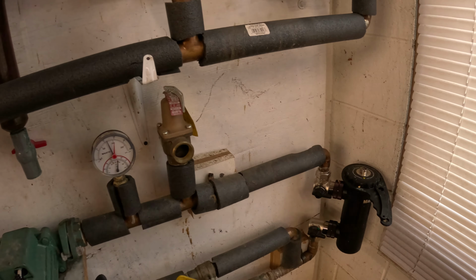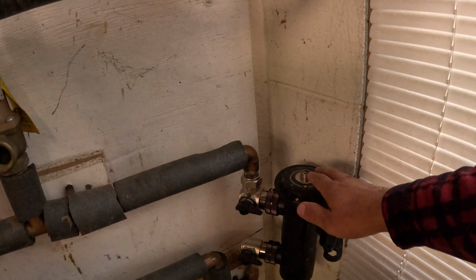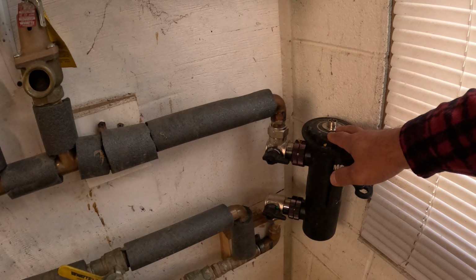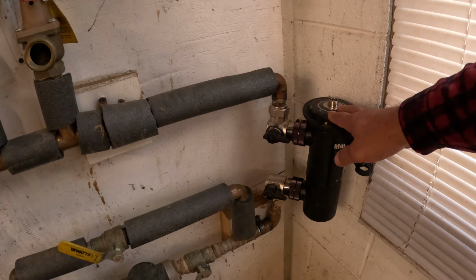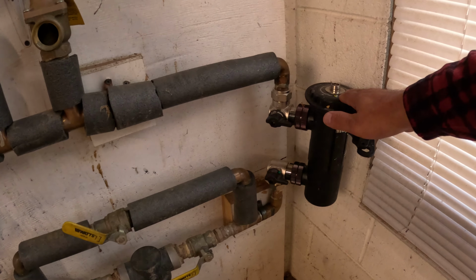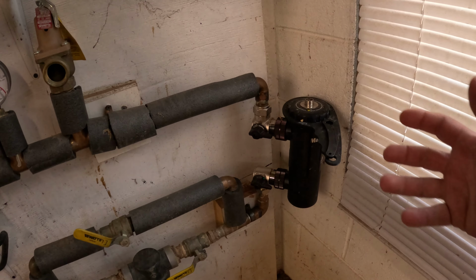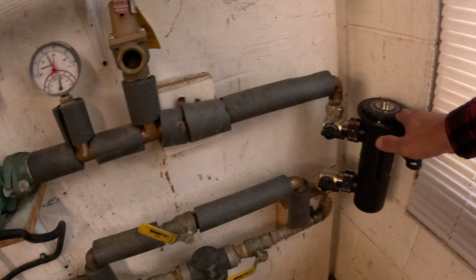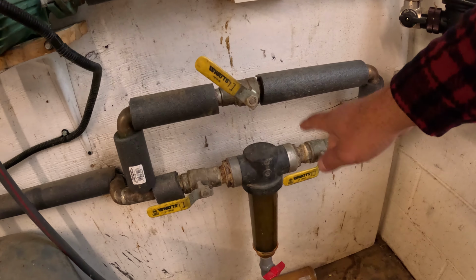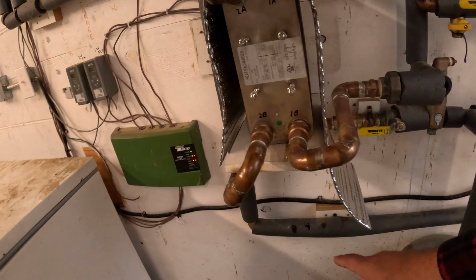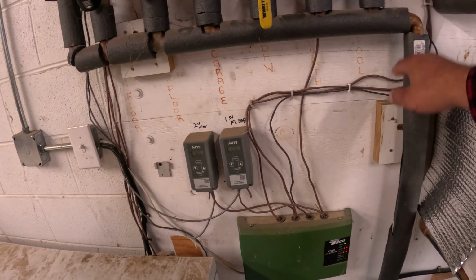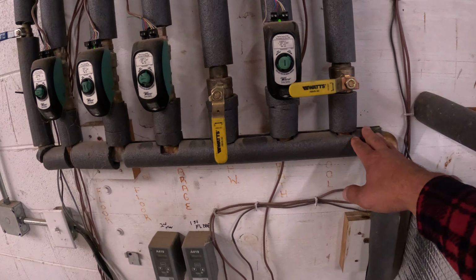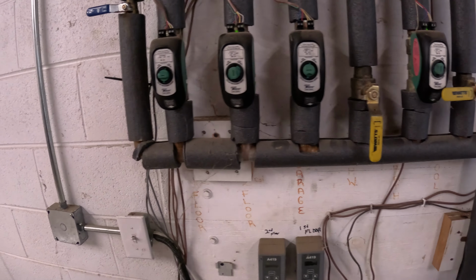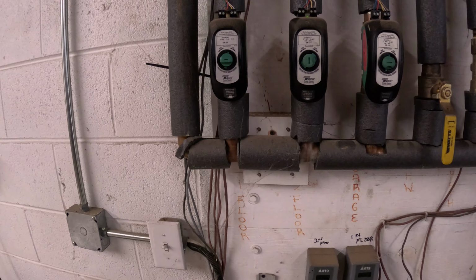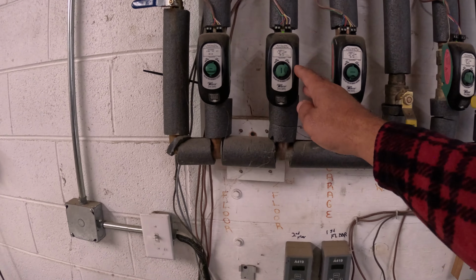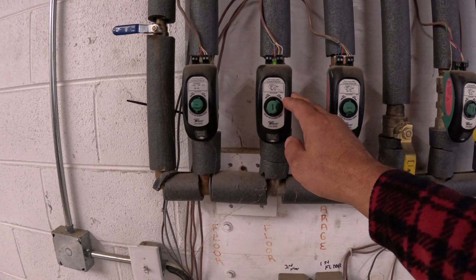So I actually come in, and this really solved the problem. So this is actually almost like a magnetic filter. So it collects all of that black stuff that would normally corrode the inside of your pipes into this, and I just clean it. I pull that out, and it's a magnet, and I wipe it off. Then another kind of system like we had before, where filter bypass. Then this comes up, and then I have a zone controller. So essentially we got multiple zones in the house. So we've got a 1st floor zone, and this is controlled by that thermostat. 2nd floor, and that's controlled by that thermostat, and as you can see, it's calling for heat right now with the green dot.